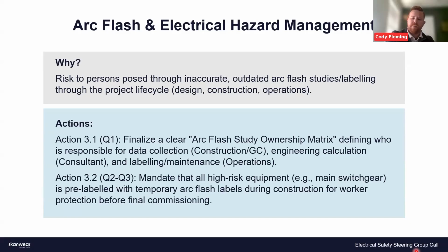There's also a mandate that all high-risk equipment be pre-labeled with temporary arc flash labels during construction for worker protection before final commissioning. This is a requirement governed by several standards: NFPA 70E Article 130 discusses field labeling and safety training, NFPA 70 (NEC) discusses equipment rating versus fault current, and ANSI and NETA ATS cover verification of circuit breaker settings.